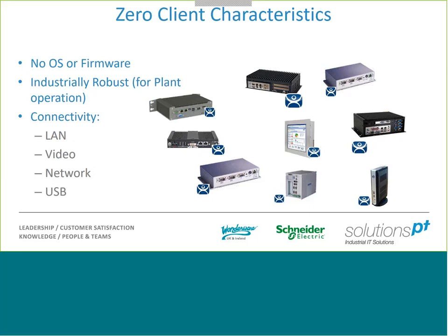In the middle there we've got a panel PC, so that can be a thin client too. So some people like those if you have a failure with a client and you're not sure whether it's the display that's faulty or the thin client that sits behind it. By utilising an all-in-one solution, it means that the operator's just got to swap one device to swap over without trying to fault find. So one of the great advantages of Thin Manager is it is very easy to replace a thin client.